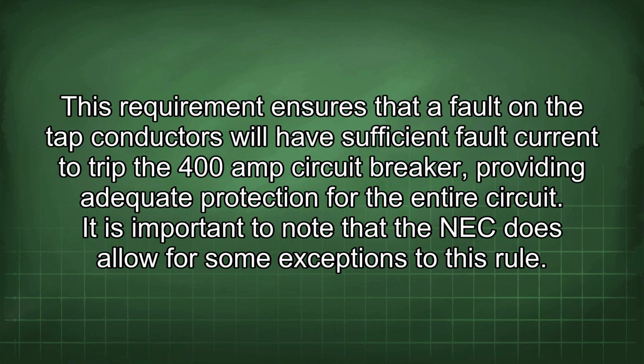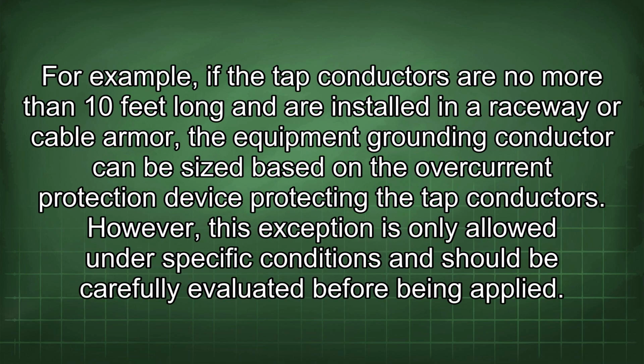This requirement ensures that a fault on the tap conductors will have sufficient fault current to trip the 400-amp circuit breaker, providing adequate protection for the entire circuit. It is important to note that the NEC does allow for some exceptions to this rule. For example, if the tap conductors are no more than 10 feet long and are installed in a raceway or cable armor, the equipment grounding conductor can be sized based on the overcurrent protection device protecting the tap conductors. However, this exception is only allowed under specific conditions and should be carefully evaluated before being applied.